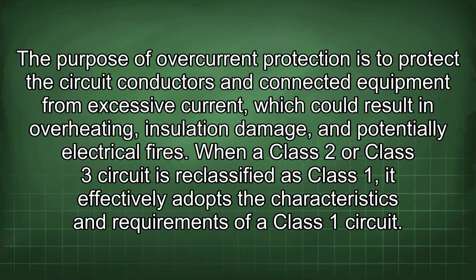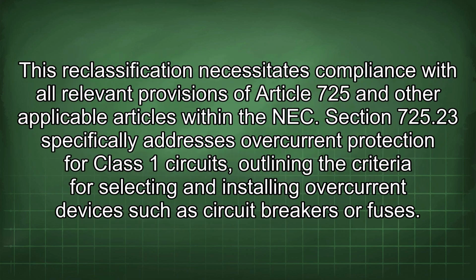When a Class 2 or Class 3 circuit is reclassified as Class 1, it effectively adopts the characteristics and requirements of a Class 1 circuit. This reclassification necessitates compliance with all relevant provisions of Article 725 and other applicable articles within the NEC.